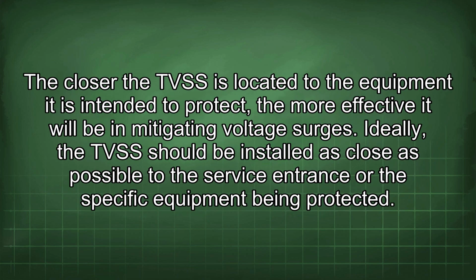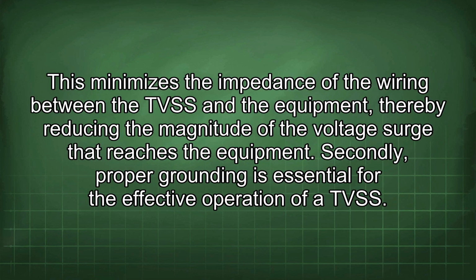The closer the TVSS is located to the equipment it is intended to protect, the more effective it will be in mitigating voltage surges. Ideally, the TVSS should be installed as close as possible to the service entrance or the specific equipment being protected. This minimizes the impedance of the wire in between the TVSS and the equipment, thereby reducing the magnitude of the voltage surge that reaches the equipment.